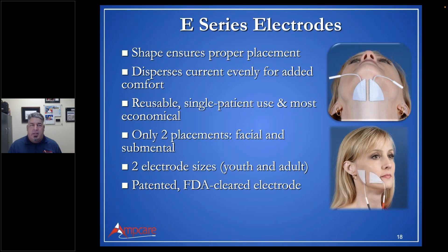It is a class 2 medical device, and it is patented for that. And here's a dispersion plate, and I think this is important for everyone. If you look at the pie-shaped electrode of Ampcare on the left and the small traditional round, this is what's typically used in a lot of physical therapy, occupational therapy, but also most of the speech therapy electrical stim devices use this traditional round. If you just have a traditional round electrode and that lead wire goes right into the pad, you're going to have a high level of intense sensation at where the lead wire goes into that electrode.